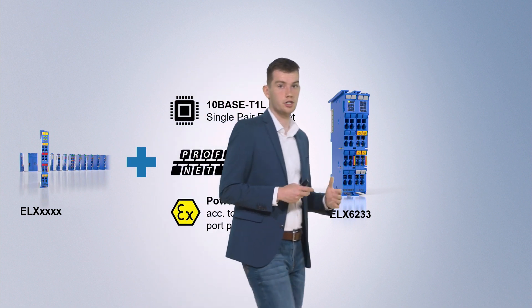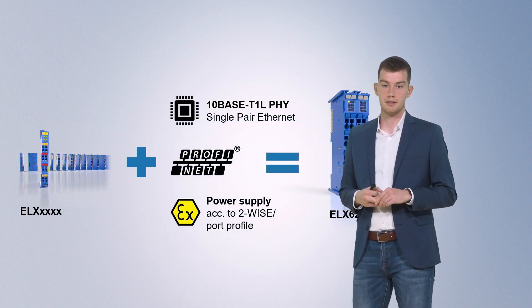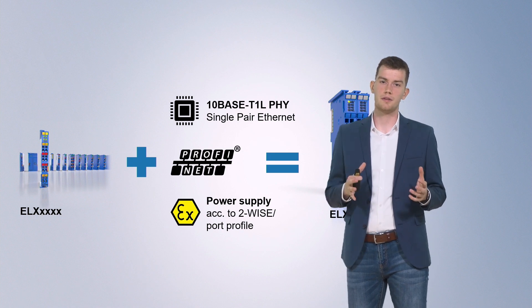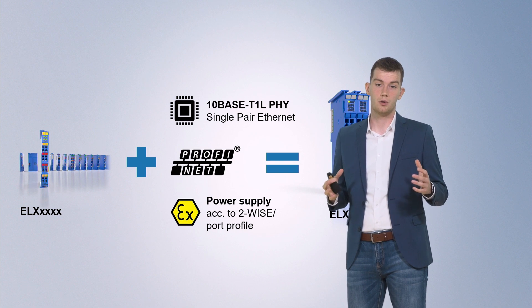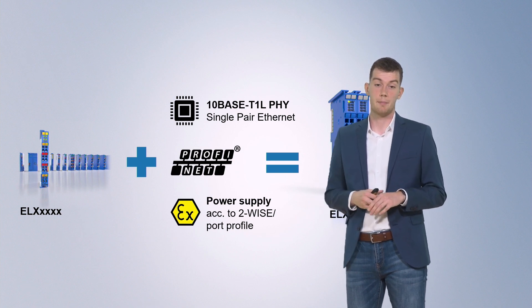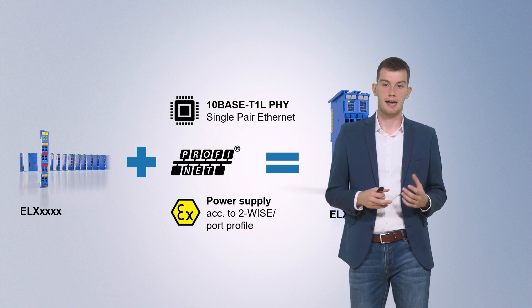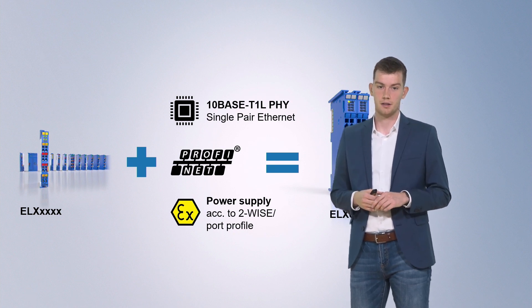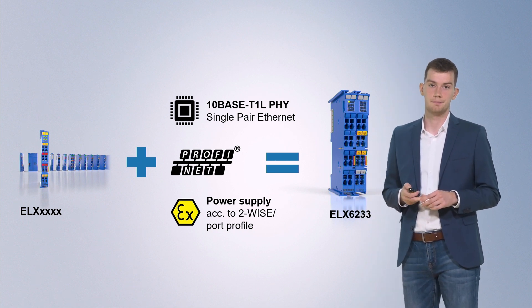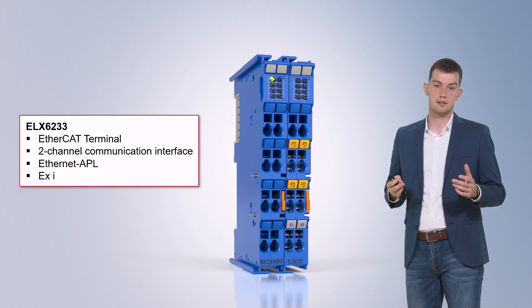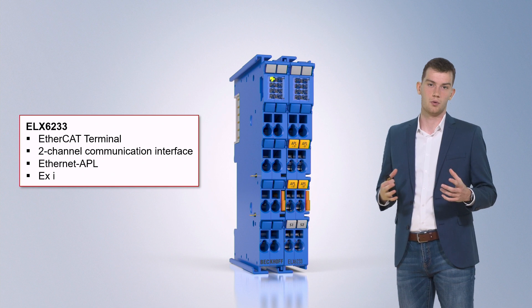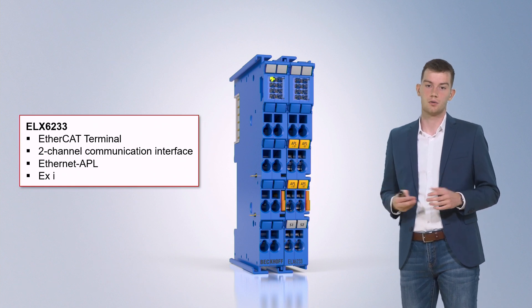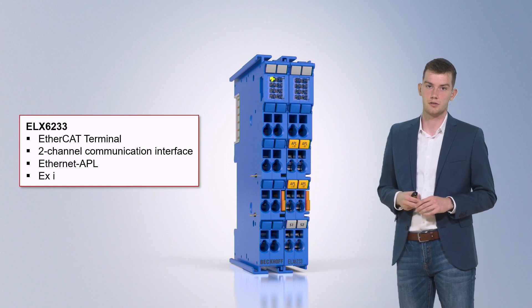So what is the idea from Beckhoff? How do we address these requirements? We take a different, modular, and more flexible approach. Our development is based on the ELX series — our ELX portfolio, which is designed for intrinsically safe applications. We combine the know-how in explosion protection with a PROFINET controller and the corresponding Ethernet PHY for single-pair Ethernet. As a result, we have the ELX 6233, which joins the well-known EtherCAT portfolio from Beckhoff. It has two APL channels and is compliant to the 2-WISE standard for explosion protection zones in intrinsically safe applications.